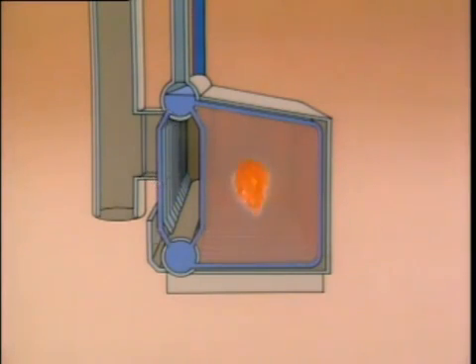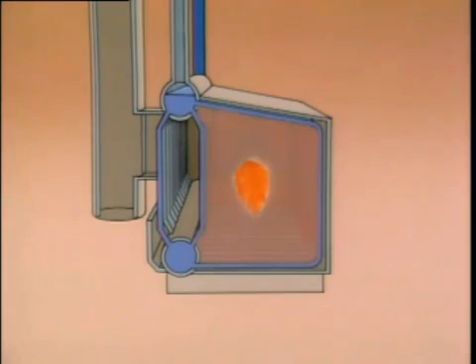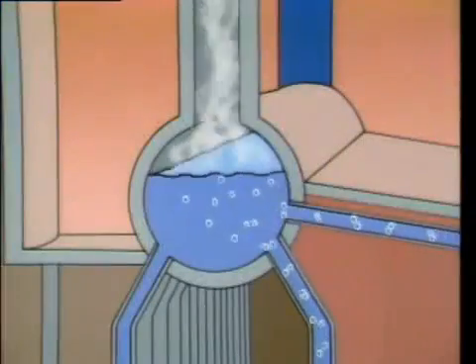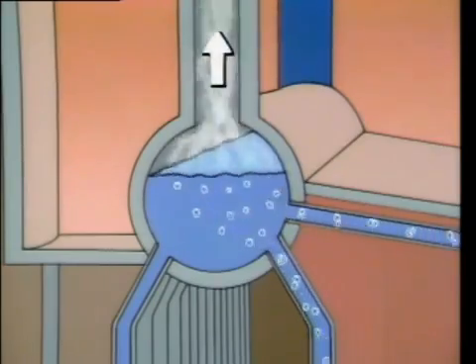The lower drum is often referred to as the mud drum. From the lower drum, the water is distributed to the water tubes surrounding the combustion area. As the water in the tubes is heated, a steam-water mixture is produced. The steam-water mixture enters the upper drum. The steam is separated from the water and routed through the steam outlet and into the plant.